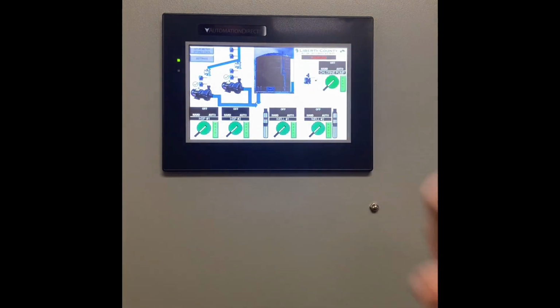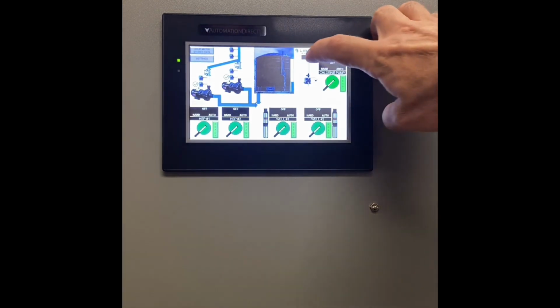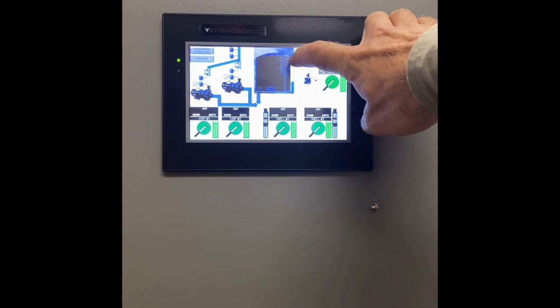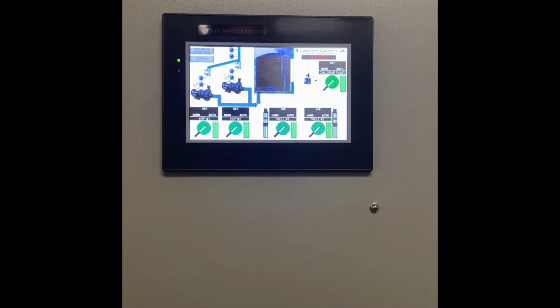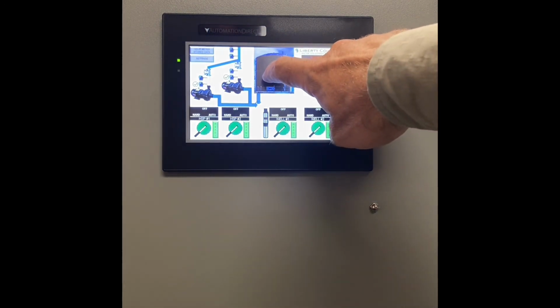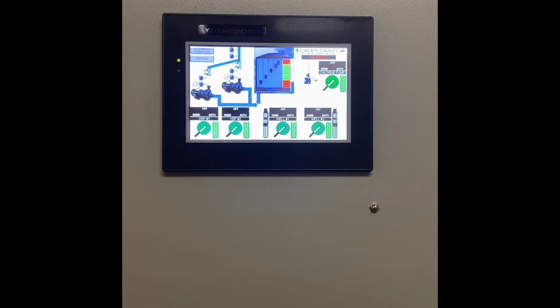We have our groundwater storage tank in the center, and you'll notice that I have a blue bar raising up on the side. Now, we do not have an analog input on this actually feeding back what storage tank is. What I am doing, if I touch this, it'll bring up a representation of the floats. You'll notice that each float is labeled on the right. The 2 alarm floats are labeled in red, and the middle 3, which will run the wells, are labeled in green. It's just a way of delineating which floats control the motors and which floats control alarm conditions.